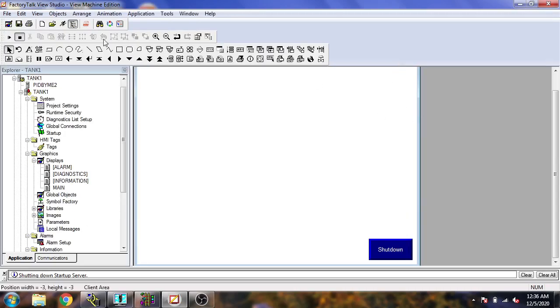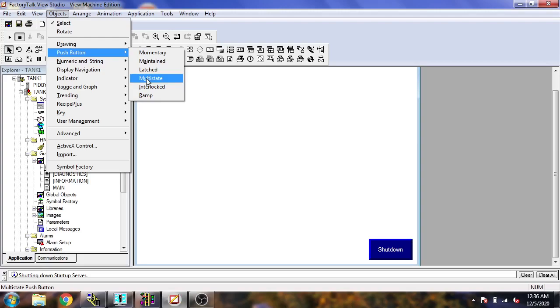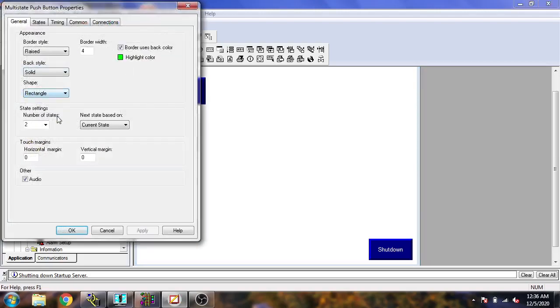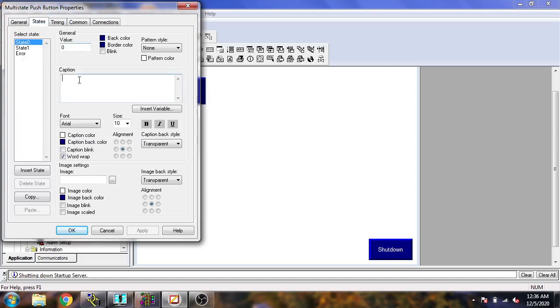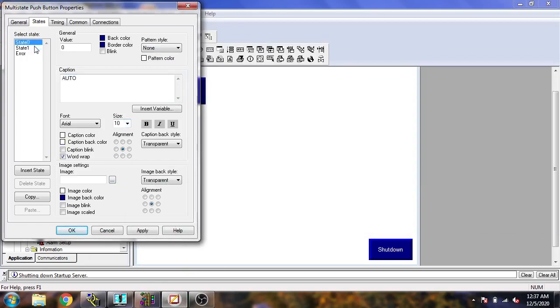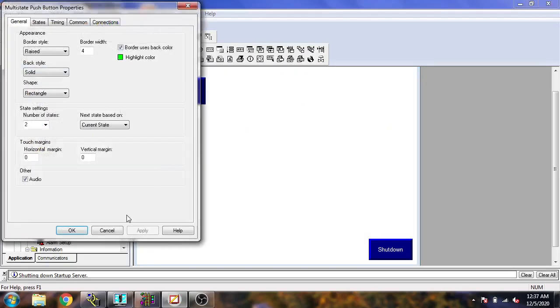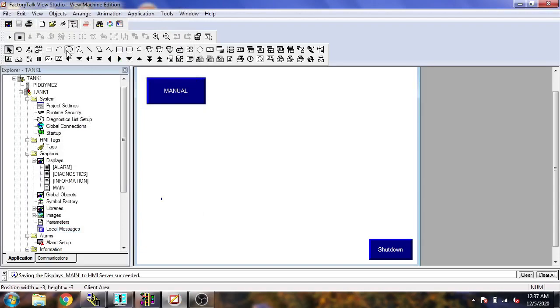First of all I'm going to select a push button — specifically a multi-state push button. It currently has two states: state zero means Auto and state one means Manual. I'm selecting a white color for it. I'm using our Auto Manual tag, giving it the Auto state, and making a connection for Manual as well. So our manual button has now been created.